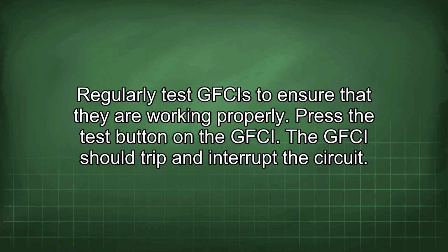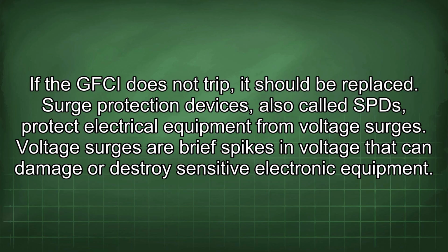Regularly test GFCIs to ensure that they are working properly. Press the test button on the GFCI. The GFCI should trip and interrupt the circuit. If the GFCI does not trip, it should be replaced.